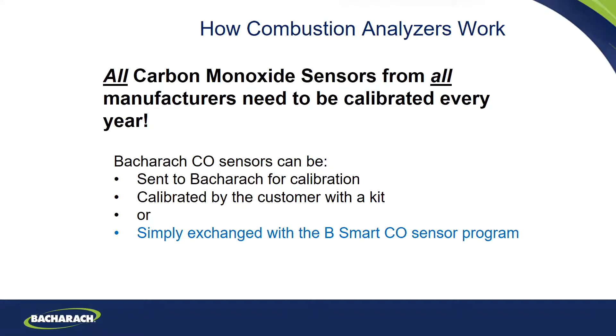You open the package, it has a sensor in it. You take your old sensor out and put it in the package, take the new sensor out of the package and put it in your unit, and then there'll be a little piece of paper. Don't throw that paper away, it's a code that you put on the front so you're calibrated. Then since the old sensor's in there, you seal this up - it's pre-stamped, pre-addressed. Just throw it in your mailbox or the post office box, and you're good.